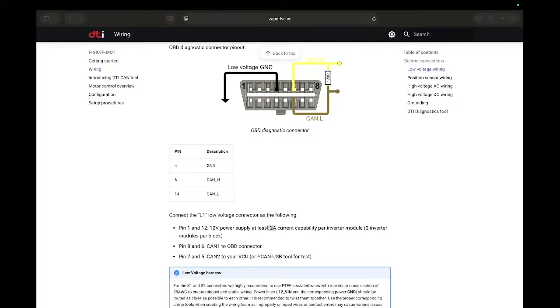Regarding the wiring, there is something more to mention, which is the routing. I'll show you the actual principle a little bit later, but I mention now that the plus and minus wires of the low voltage power supply should be routed as close as possible to each other - connect them with zip ties or twist them to make a fully connected, very close connection to each other to be robust and noise proof.